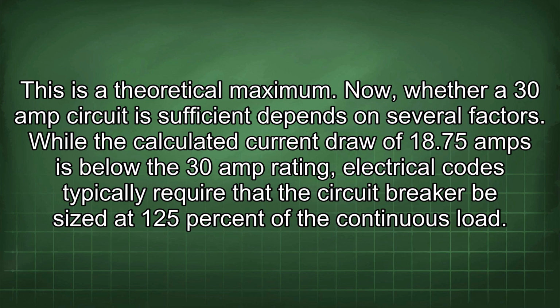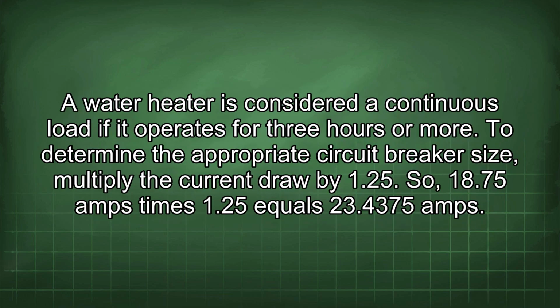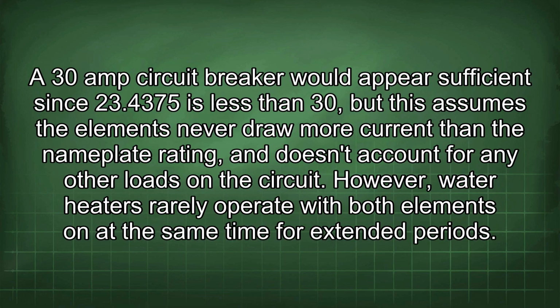While the calculated current draw of 18.75 amps is below the 30 amp rating, electrical codes typically require that the circuit breaker be sized at 125% of the continuous load. A water heater is considered a continuous load if it operates for 3 hours or more. To determine the appropriate circuit breaker size, multiply the current draw by 1.25. So 18.75 amps times 1.25 equals 23.4375 amps.